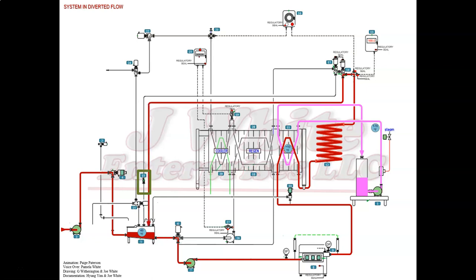The sight glass in the leak detect line monitors the condition of the flow divert valve while the HTST is in diverted flow. If product is seen in the sight glass, it is an indication that the flow divert valve is leaking out the top port, allowing raw product into the pasteurized side of the HTST.